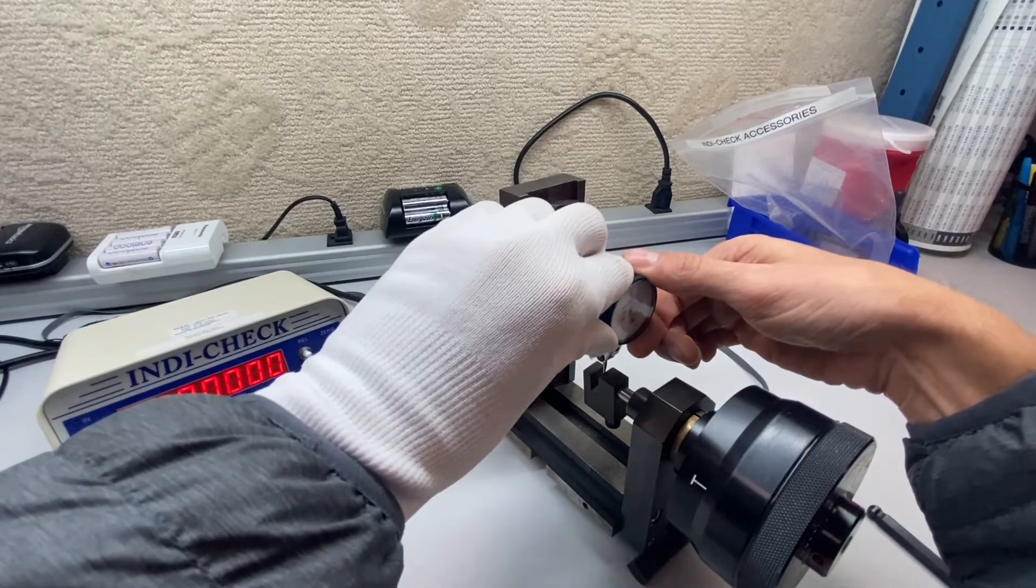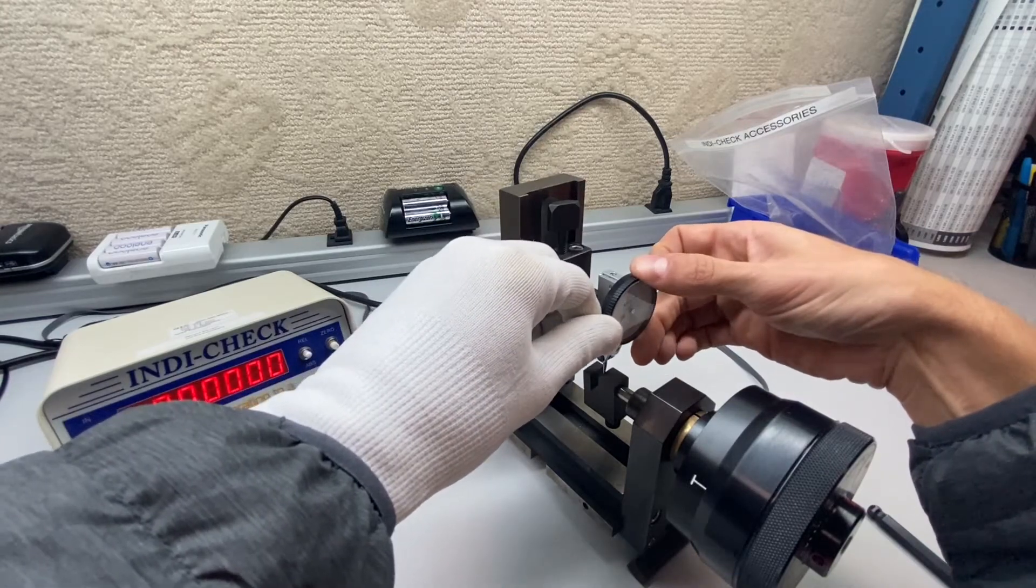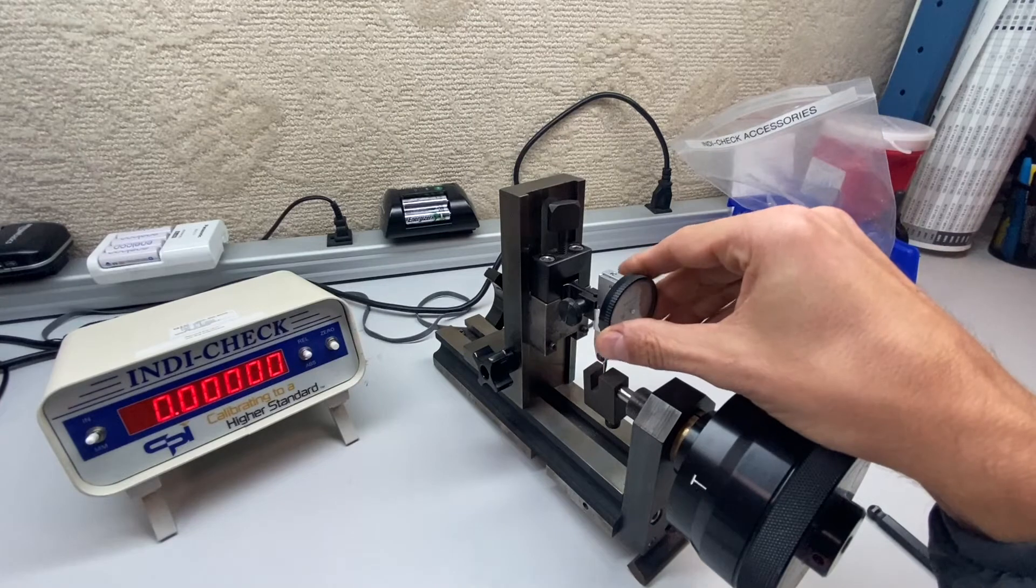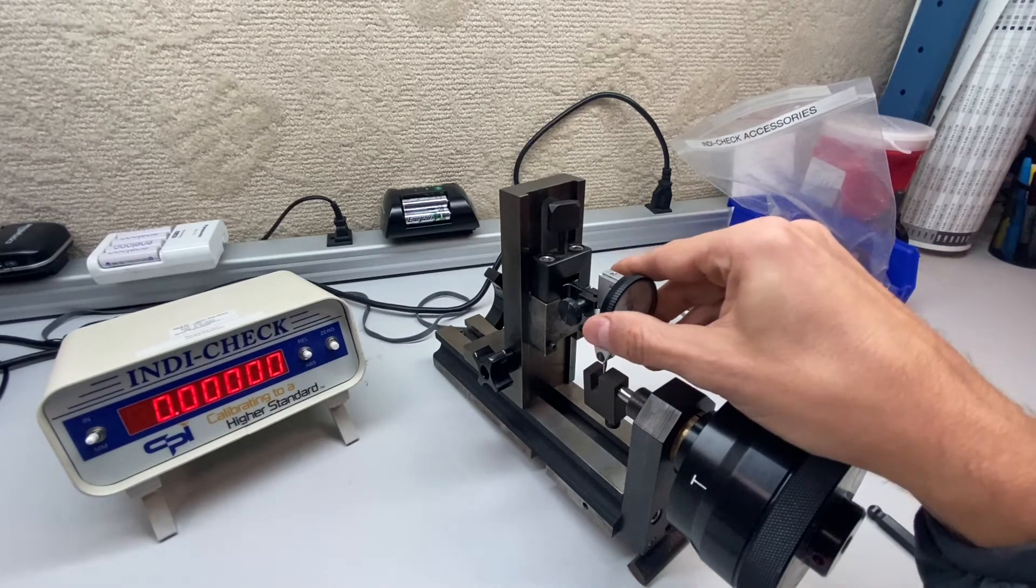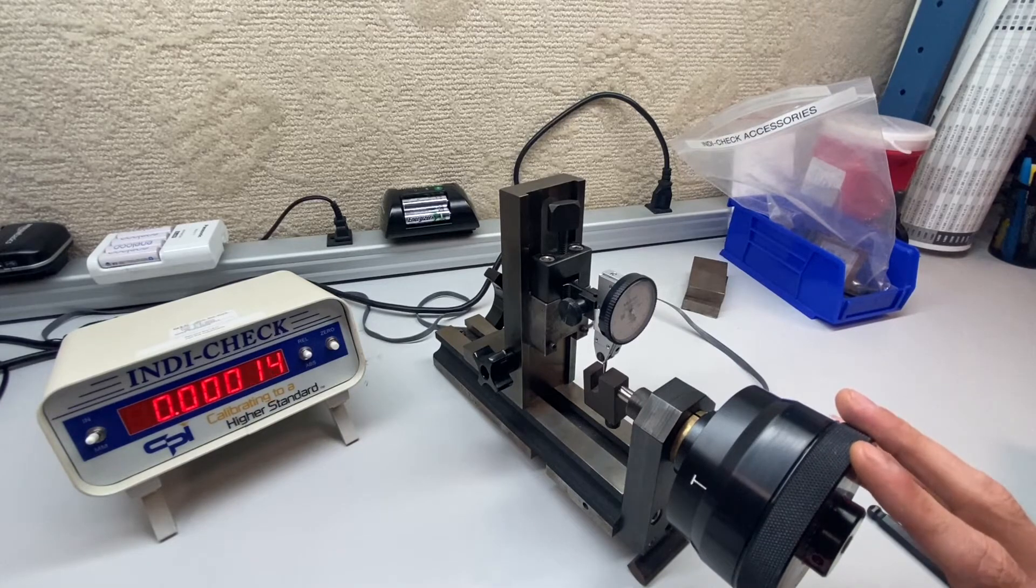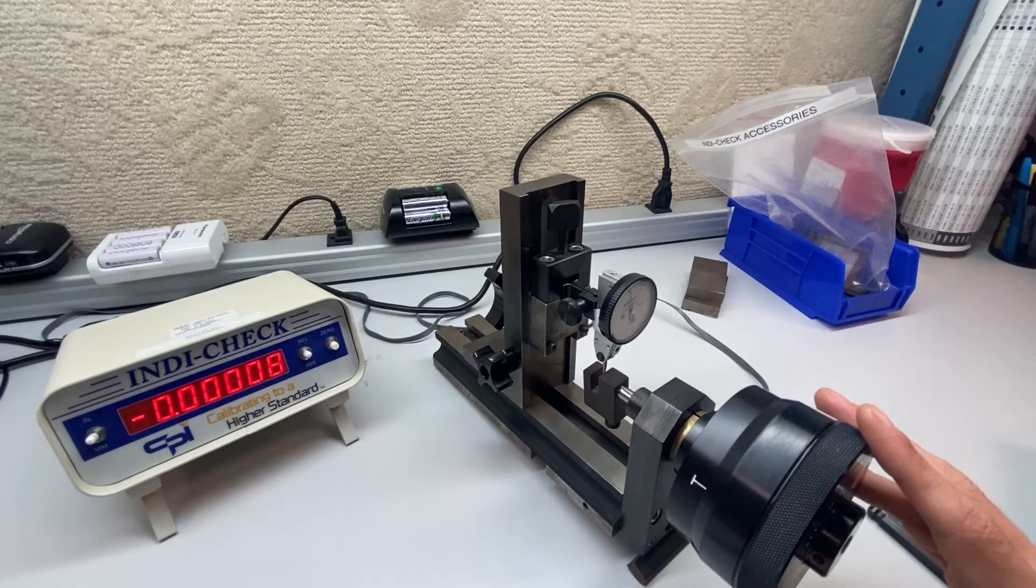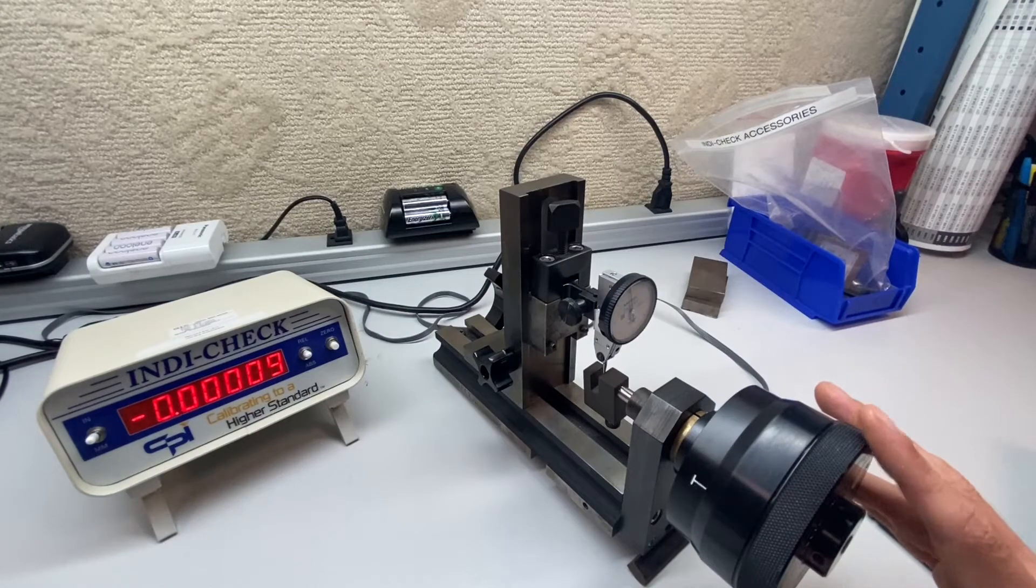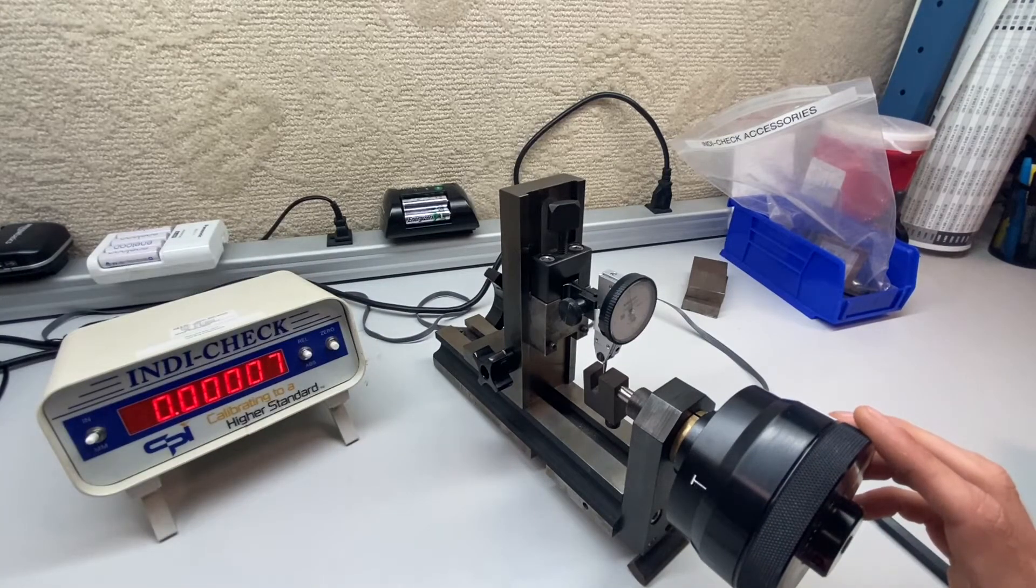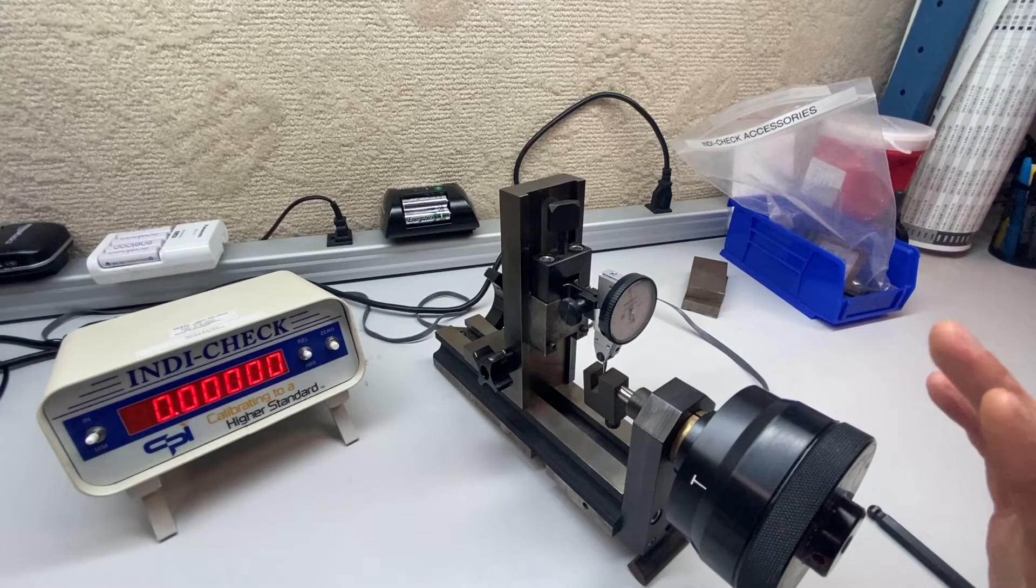We'll need to get a hold of this. Gently touch that so I don't ruin the reading. This is where good fixturing really helps. We'll get it roughly right and then I'll just adjust this. So coming up on it we'll get up to zero. And I'm perfectly aligning my head with the needle covering up the number. Come back and check my zero. I like it and I'm reading the Indi-Check. It's good.